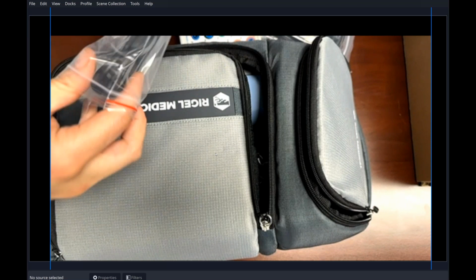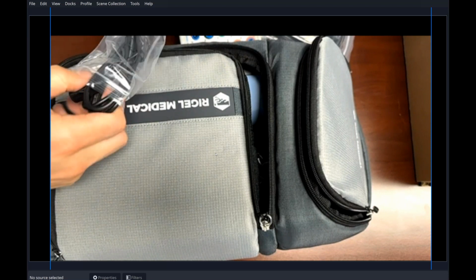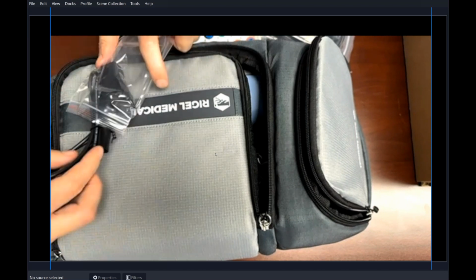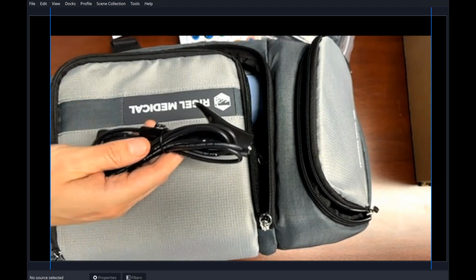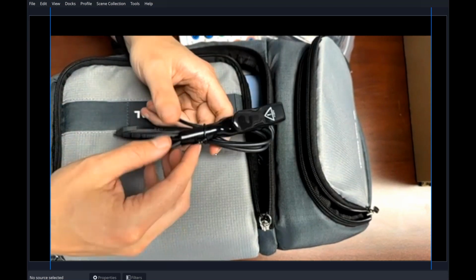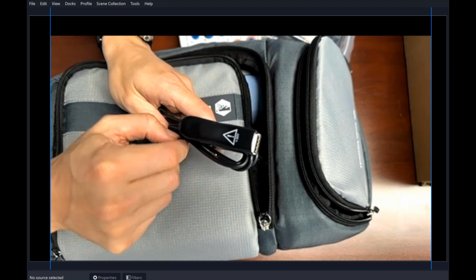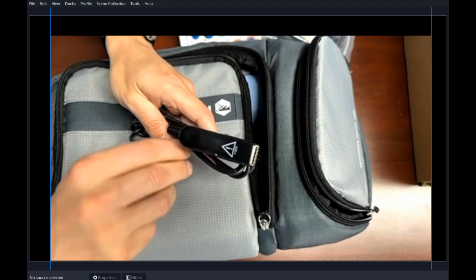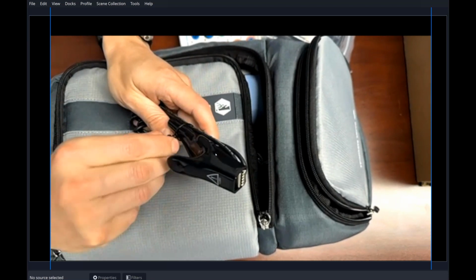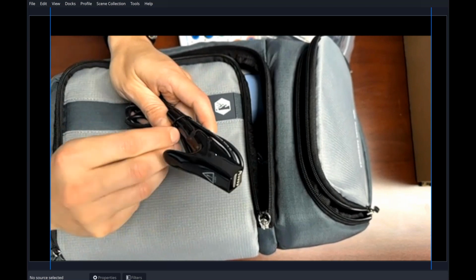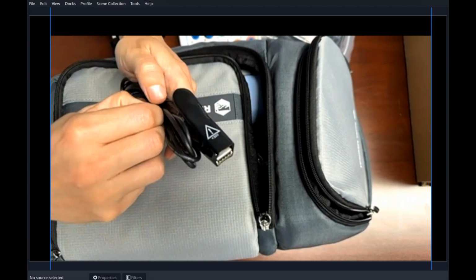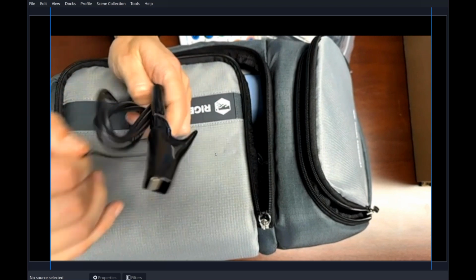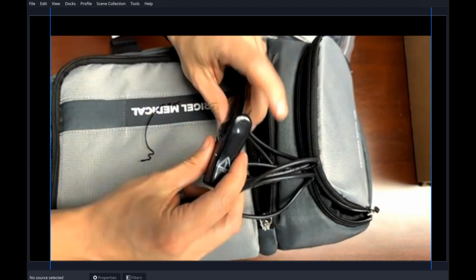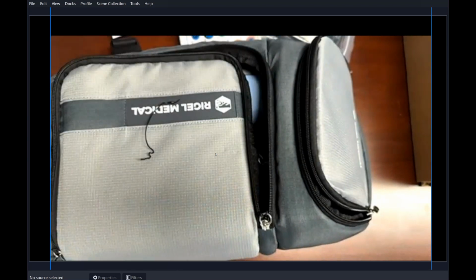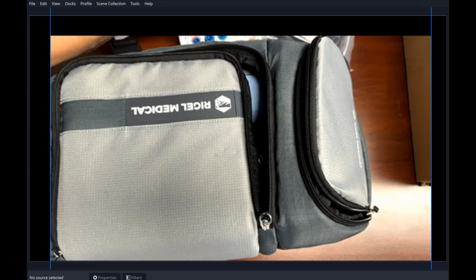There are a couple of ground bond leads. This helps if you're doing different types of devices, but also for point-to-point testing, you've got 2 different leads that come with it. So we've got the crocodile clip style ground bond lead. They're both 1.5 meters, roughly 5 feet each lead. So that's the first lead. We've got the croc clip connected onto the rear of the device.